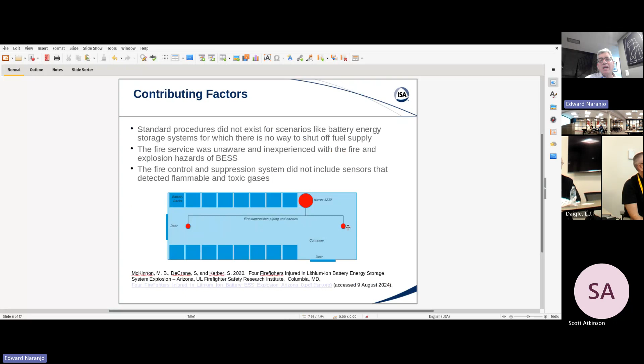Looking at the actual schematic of the container, even though there was an extinguisher in place with two points of release, there were no sensors for flammable and toxic gases. You may have had an event that triggers sprinklers or the offloading of a fire extinguishant, but without a flammable or toxic gas detector, you would never be able to extinguish that fire. There's definitely not the type of sensing mechanism required.